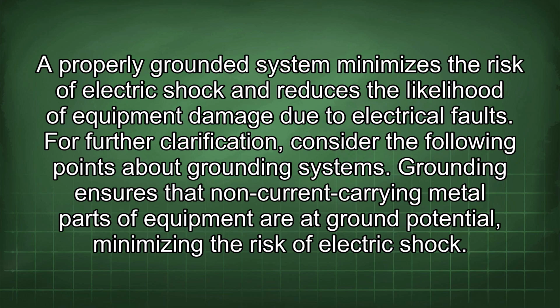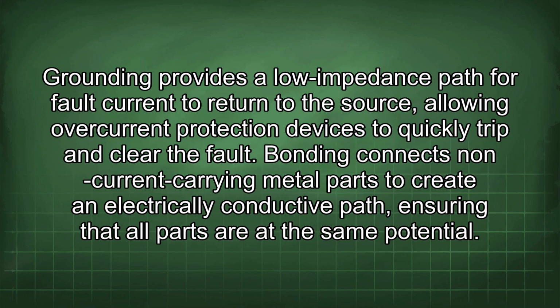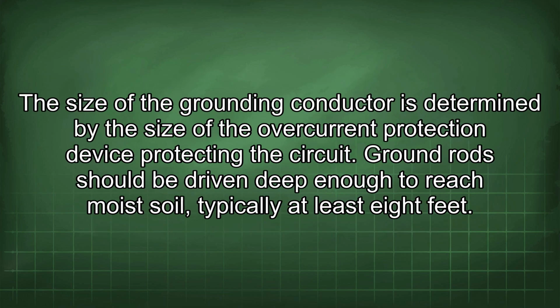For further clarification, consider the following points about grounding systems. Grounding ensures that non-current carrying metal parts of equipment are at ground potential, minimizing the risk of electric shock. Grounding provides a low impedance path for fault current to return to the source, allowing overcurrent protection devices to quickly trip and clear the fault. Bonding connects non-current carrying metal parts to create an electrically conductive path, ensuring that all parts are at the same potential. The size of the grounding conductor is determined by the size of the overcurrent protection device protecting the circuit.